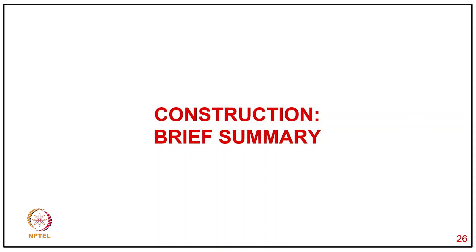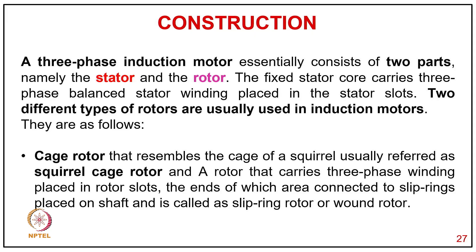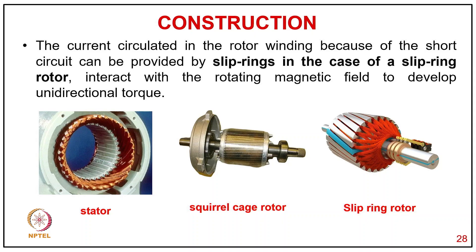A three-phase induction motor essentially consists of two parts: the stator and the rotor. The fixed stator core carries three-phase balanced stator windings placed in stator slots. Two different types of rotor are used: the cage rotor, which resembles a squirrel cage and is usually referred to as the squirrel cage rotor, and a wound rotor that carries three-phase winding placed in rotor slots with ends connected to slip rings on the shaft.